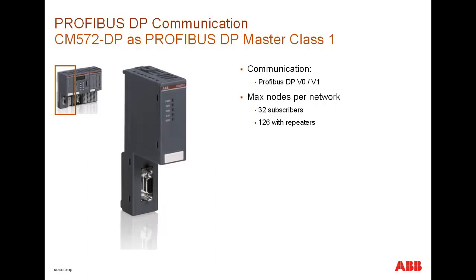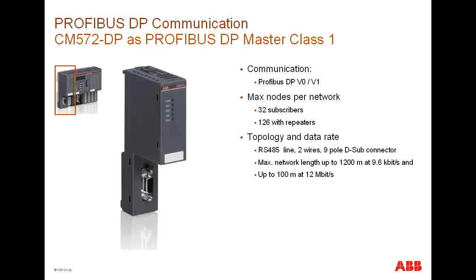Segment-to-segment connection is possible with the help of PROFIBUS repeaters. In this way, one could go up to 125 slaves. The stations are connected in line topology, and the transmission rate depends on the segment length. The fastest rate is 12 megabits per second for a distance of 100 meters or less.